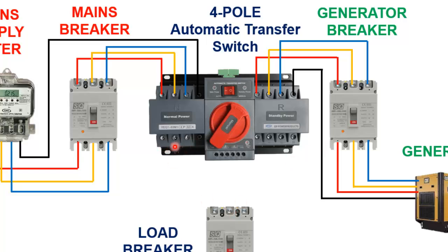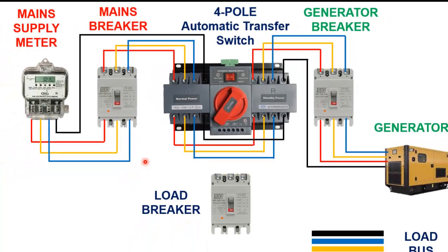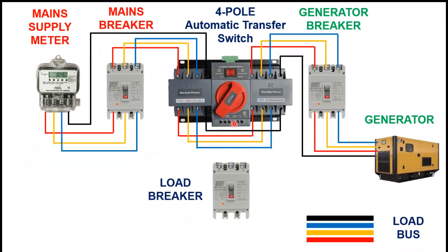Now connect all three phases and neutral of both outputs with each other, or simply short both outputs of ATS in proper sequence. Now make the connection from the output of ATS with the input side of the load circuit breaker. Now finally connect the output of the load circuit breaker with the load bus.